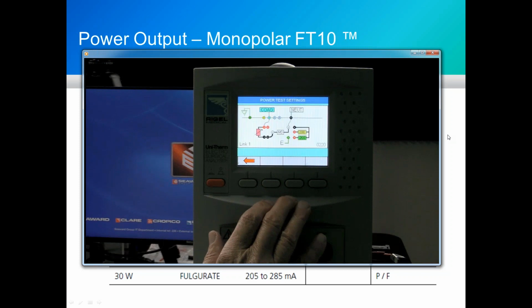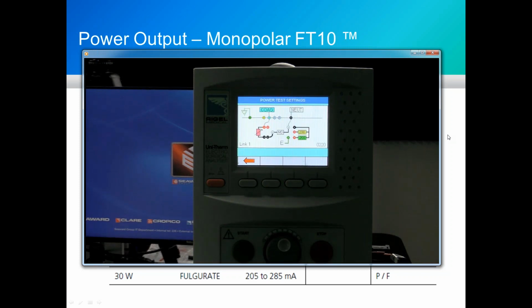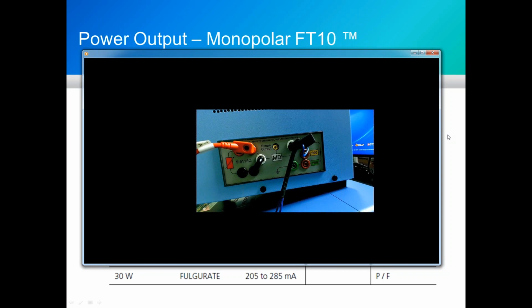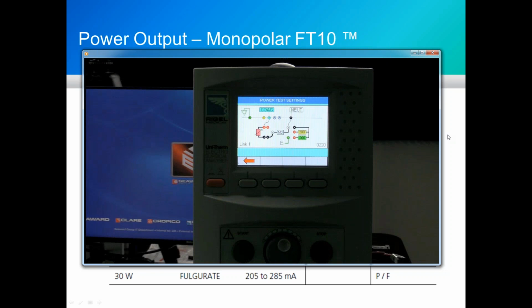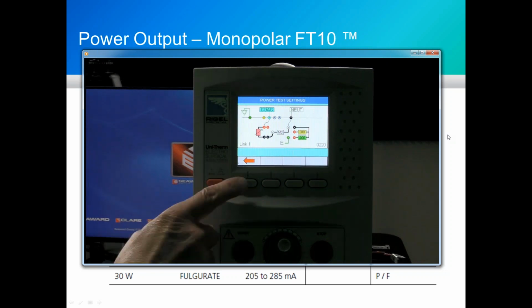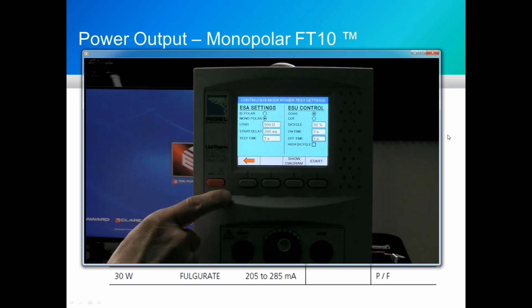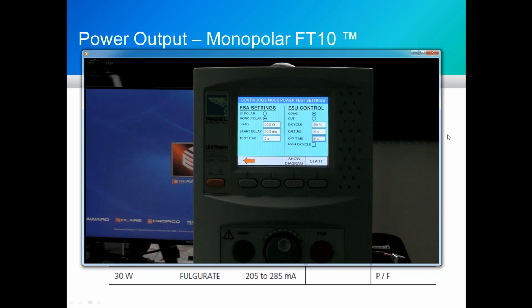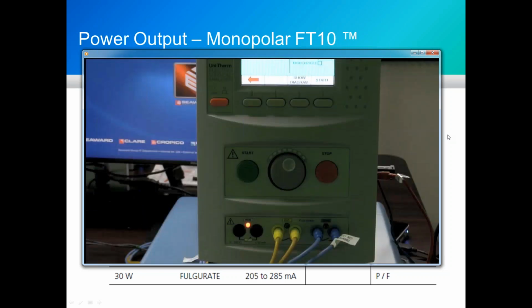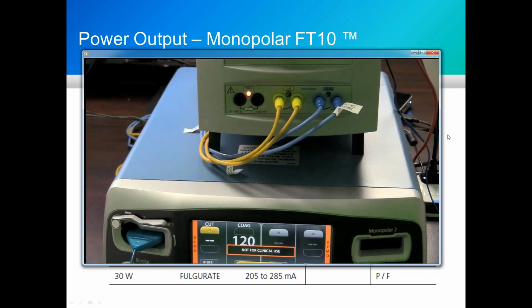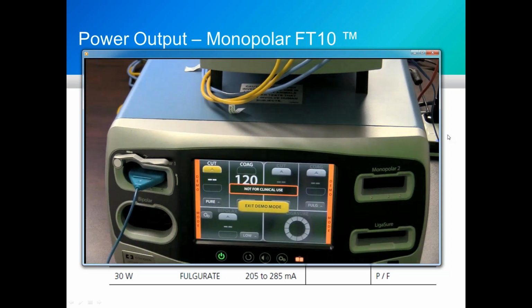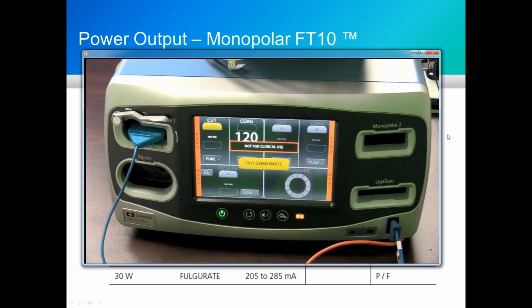So here's the show diagram function that shows the active electrode coming out, going through that resistor that we just set for 500 ohms, and then back through the current transformer to the patient return. I'm going to hit the start button twice. As I do that, you'll see that quadrant on the display become active.